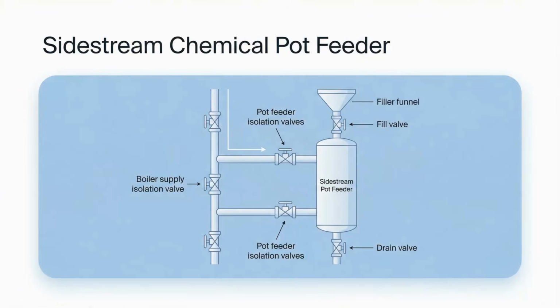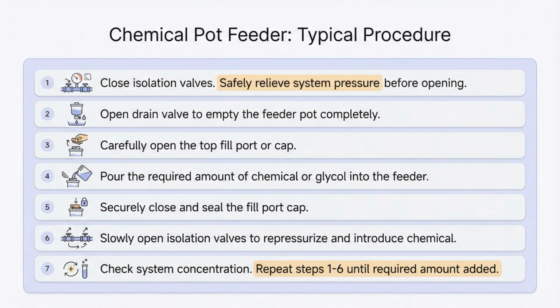One way to add glycol to small systems is a side stream chemical pot feeder. The visual layout is basically a small vessel piped into the system with isolation valves, a fill point with funnel, and a drain. It's used when the system will be fully glycol water solution and you need a controlled way to introduce concentrated glycol. The typical pot feeder procedure is: fill the system with water when temperatures won't freeze it, close the pot isolation valves, open the pot drain to relieve pressure and drain, close the drain and open the fill, pour in 100% glycol until full, then close the filler valve and open isolation valves while closing the boiler supply valve and pump to push glycol into the system. Then repeat until the required amount is added.